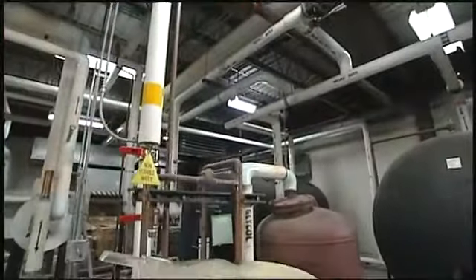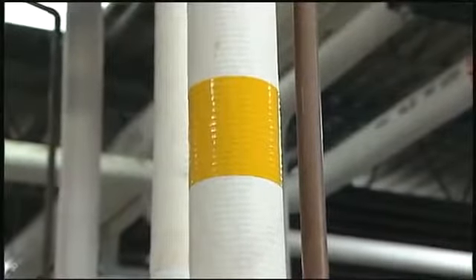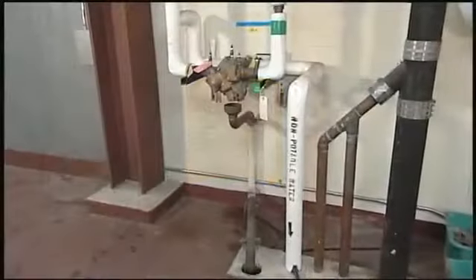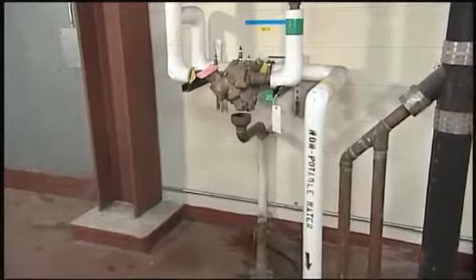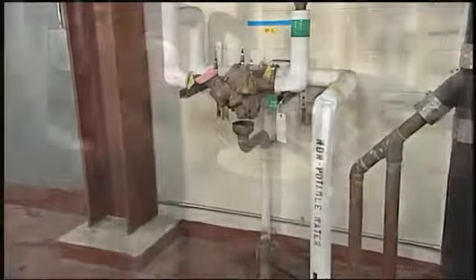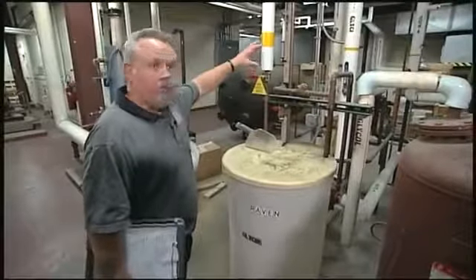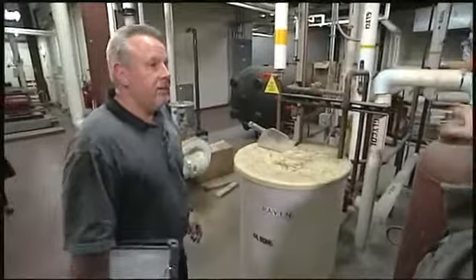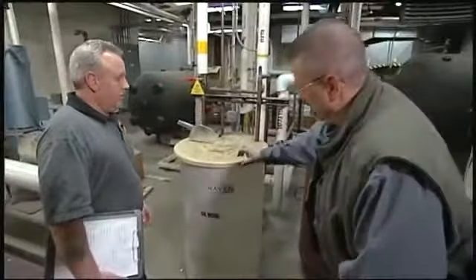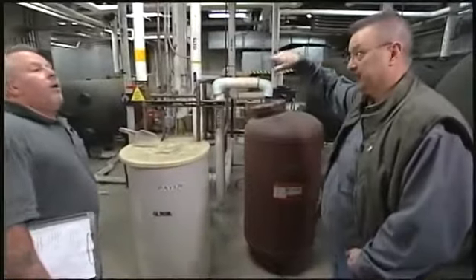Now what we need to do is go back and verify that this pipe is identified with the yellow bands and/or unsafe verbiage, non-potable, back to the high hazard backflow preventer where you can continually get the water supply to this fixture, but if pressure is lost on the supply end, that valve closes, dumps on the floor what might be downstream in the system, and our safe drinking water continues safe. Because if you didn't have that device there, you run the potential of glycol entering not only this system, but other systems throughout our community.